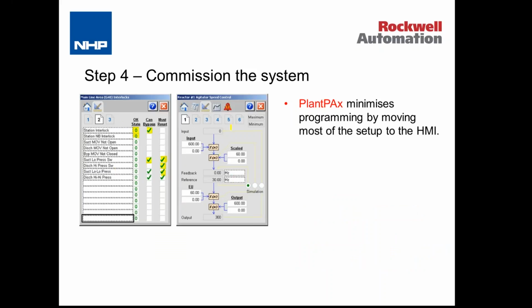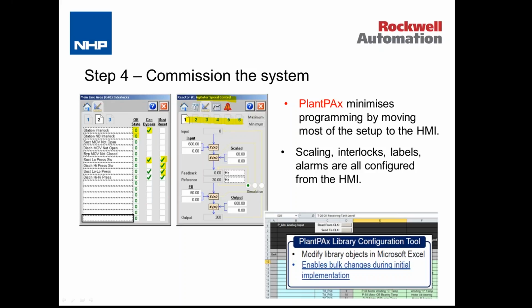The next faceplate is looking at a VSD. In this case, it's a VSD on an agitator, and you can see here that we're configuring the input scaling on the VSD, and we've actually got a number of tabs here that we can go through and do all of the configuration associated with the VSD from the screen here. So things like scaling, interlocks, labels are all configured here from the HMI. And as we mentioned, we can also access all of those things via the online configuration tool shown down the bottom there.